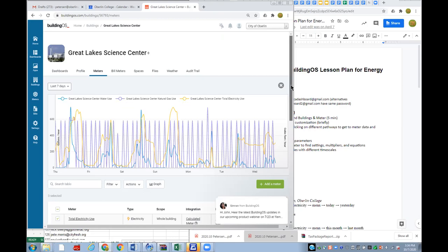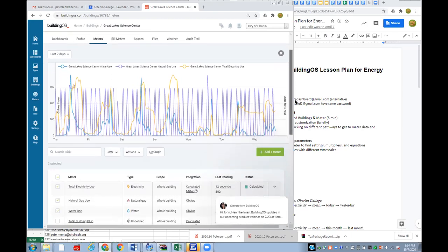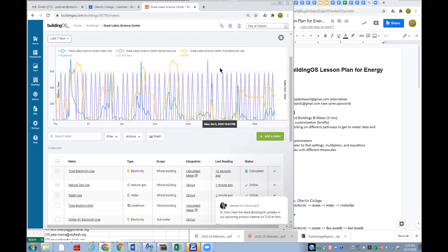Oh, okay. Right. So anyway, there's a lot of stuff to talk about with that. And I'll tell you, there's a problem with the natural gas, which has to do with the way the meter works. It actually is not spiky in its consumption like this. It's spiky in the way it reports to the meter. A certain amount of gas needs to be used before it reports gas being used, and then it sends out a pulse. And so it's just reading those pulses.